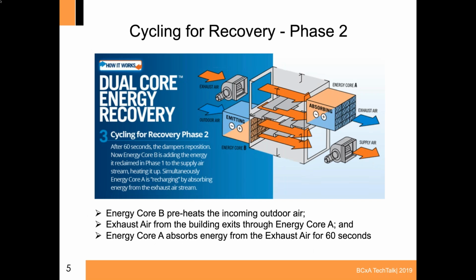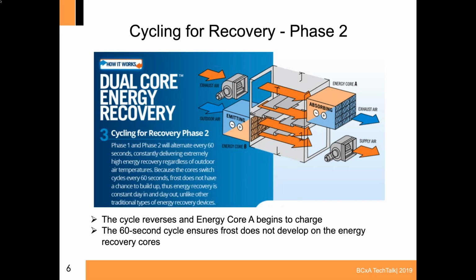When the cycle does flip over, you can see now that the exhaust air is traveling across and right through energy core A and being exhausted out. The heat is then being captured in energy core A. In the previous slide, energy core B was charging, and we now have our cold outdoor air coming across that, picking up that heat energy to preheat the cold air, and then it mixes with some return air and is supplied to the building. This cycle switches over every 60 seconds, and that helps prevent frost buildup. It's something you don't have to worry about for this type of energy recovery system, whereas with a heat wheel or other systems, you may have to have some frost prevention.